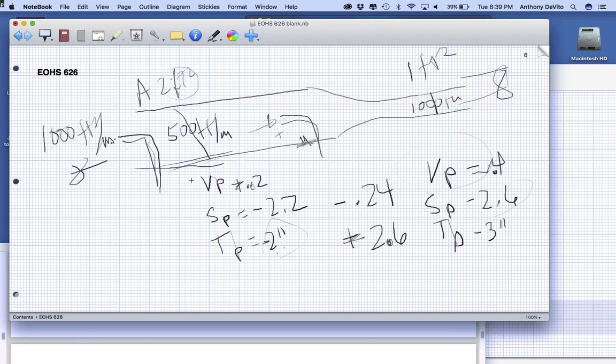What can you calculate now? You can calculate the velocity pressure as well. And the velocity pressure should come out the same. Unless there's a transition, a change in size, it's going to come out the same as we calculated for here. So the velocity pressure, unless the duct changes diameter, the air's moving at the same speed, is always the same. But the static pressure can change. And the static pressure is your loss of energy that's going to take place as you go through the system.